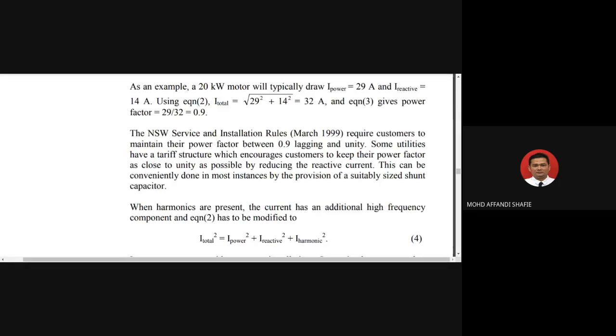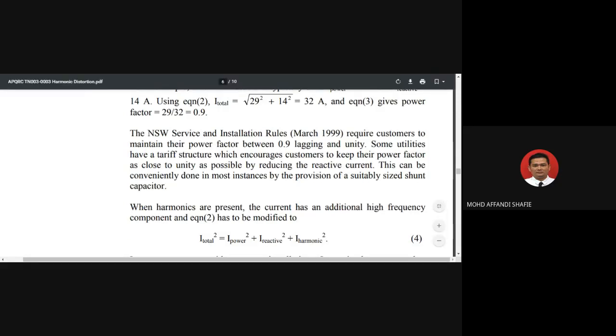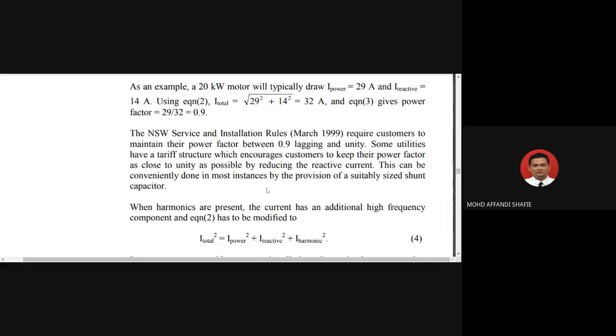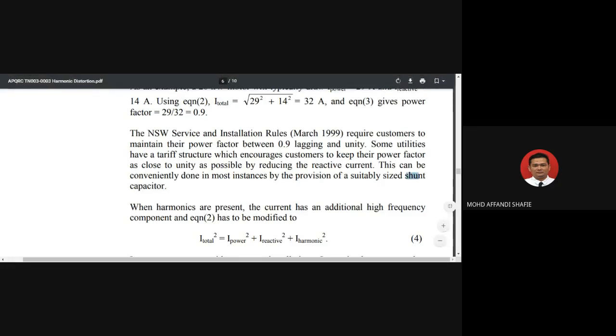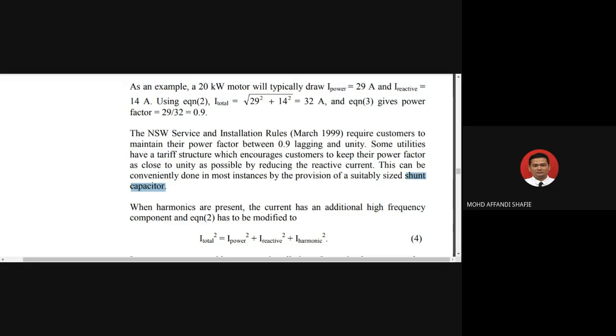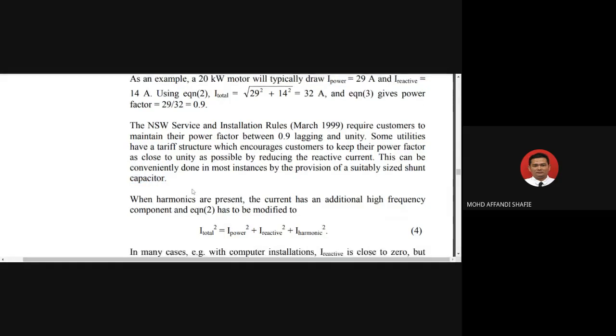Okay, some utilities have a tariff structure which encourages a customer to keep their power factor as close to unity as possible by reducing the reactive current. So it means that if you want your power factor close to unity, you must reduce the reactive current. This can be conveniently done in most instances by the provision of a suitably sized shunt capacitor. So we can control the reactive current by controlling the size of the shunt capacitor.